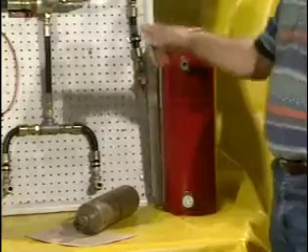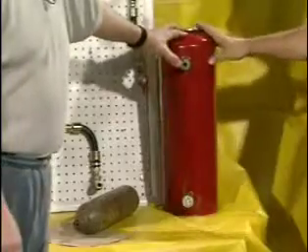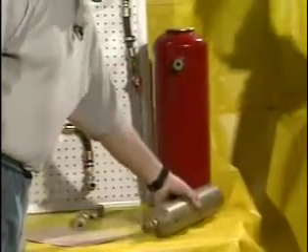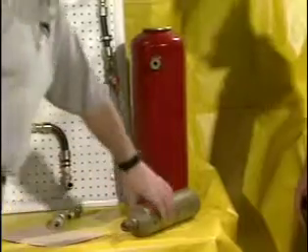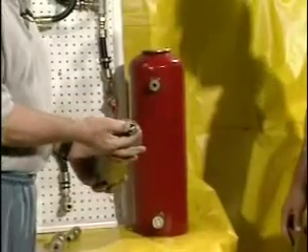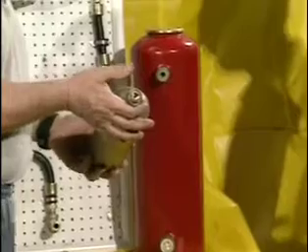Brian, we talked about the pneumatic tank. Let's talk about this tank. What's the difference between the two? This tank here is a low-temperature tank. This is fired with nitrogen. It's also a 30-pound tank. This is the largest individual Ansul tank you're going to find on mine equipment. This is the cartridge that fires that one. Same configuration on the top as on the CO2 cartridge. There's no difference, except this carries 1,800 psi.